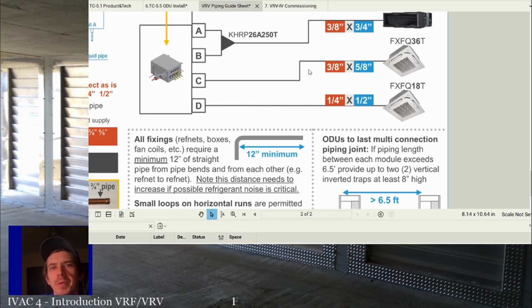But basically, if you run all the piping with tubing benders, which you should really be trying to do anyway with these systems, then you don't have to worry about the space between turns so much, because it's a nice, longer, smoother turn than, say, an actual brazed-in 90. The other thing to keep in mind with this piping is you want to minimize joints and minimize elbows.